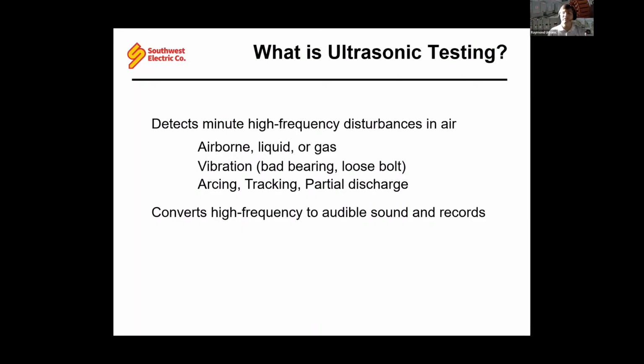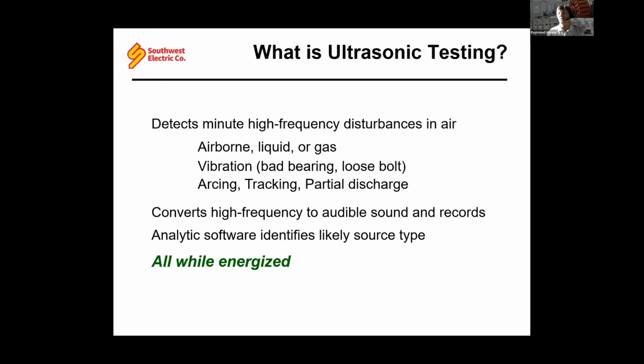And then this device converts those high frequencies into audible sounds. It can also record not just the sound, but also the frequency wave, the wavefront. And then through software, you can identify what the likely source of that disturbance is. And all this can be done while energized. So this gives you an extra insight into things the IR scan cannot do, and all of this while energized.